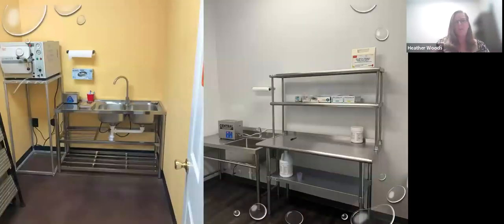Here are two examples of sterilization rooms. As Michael iterated previously, there are the following requirements. They must be used only for cleaning, disinfecting, sterilizing, storage, and related tasks. The sink must be used only for cleaning contaminated instruments. It's not used as a hand sink. There must be an ultrasonic cleaner or instrument washer included. And any items stored in the room should have cabinets or drawers that are smooth, non-porous, and wipeable.